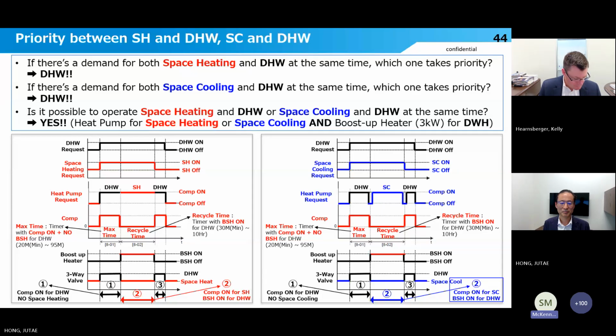So if you have a domestic hot water request, space heating will operate for a limited amount of time before shifting over to domestic. Then after the domestic max run timer is engaged, which is also variable, it will shift back to space heating, leaving a timer in place to go strictly domestic hot water, which is also variable. In turn, it will cycle back and forth between domestic and space heating or space cooling, depending on how you set it up. Sliding down the chart on the left, you can see booster heater, three-way valve, and so on. There's also electric strip heat, not only for the heat pump, which is the backup heater, but the booster heater would also be for the domestic hot water. Those can also be staged, scheduled and timed in various ways, depending on your application.